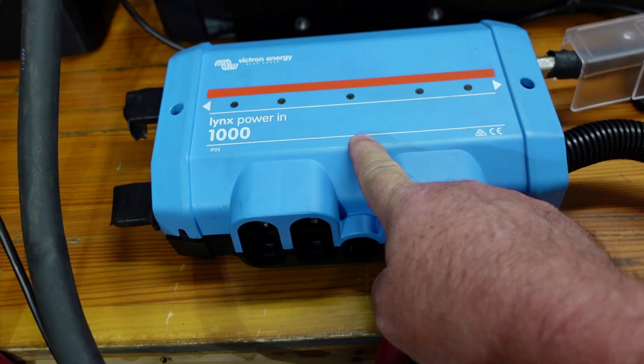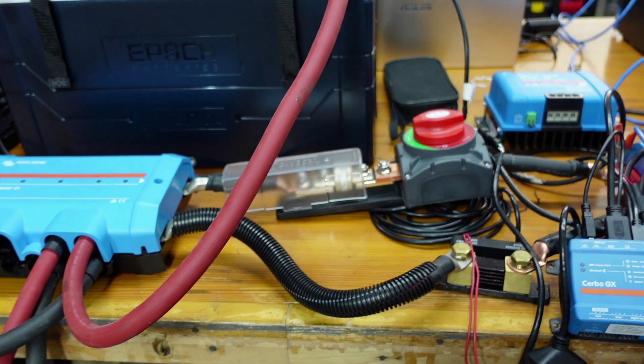When I finally install this in my boat, I'll make sure this cable, this cable, this cable, and this cable are all exactly the same length. Now, you don't really have to get all 4 cables exactly the same length - what you need is the positive and this positive to be the exact same length, and this negative and this negative to be the exact same length. If this one was 2 feet, this one was 2 feet, this one was 3 feet, and this one was 3 feet, all going to a bus bar, that's actually okay - not a problem. Then you have your main cables coming out here, so just be aware of that.